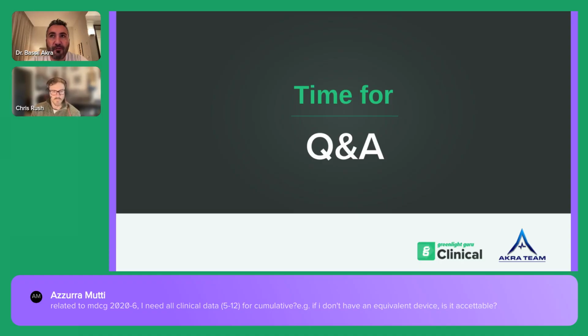So if you have a well-established technology device, and which is a legacy device as well, and you want to make use of actually lower level of evidence than rank 1 to rank 4, you are not required to have for every ranking data. You are required to have actually the data which you have. And they say you don't rely just on one source, you should rely on a storyline. So it's a cumulative combination of the multiple data set.